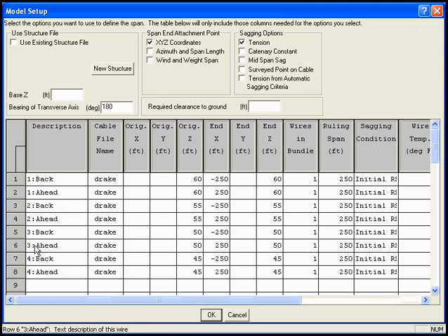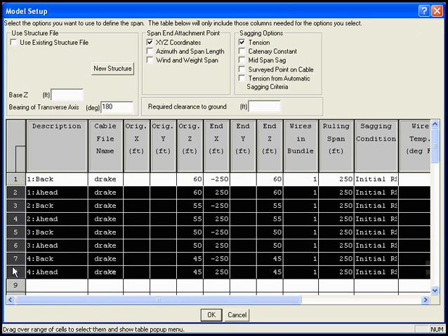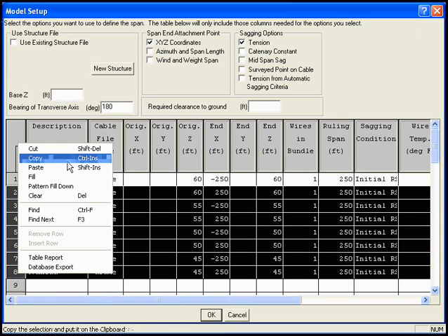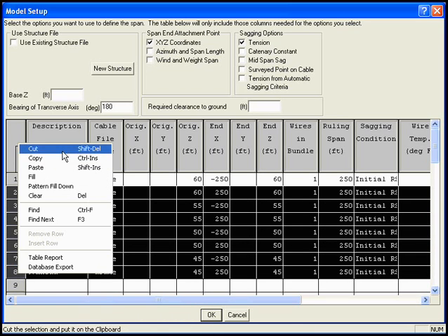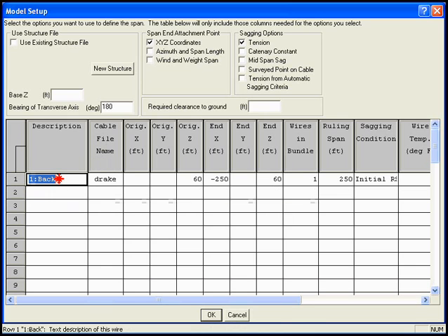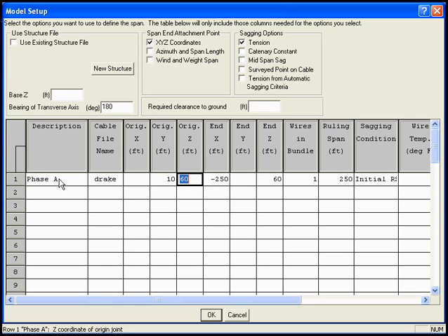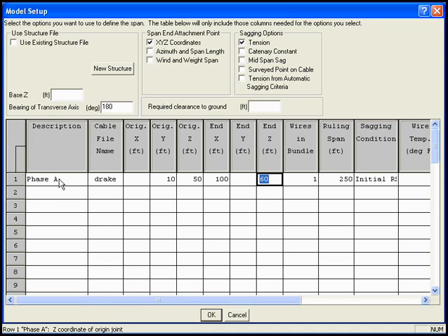It opens up the wizard. Everything is set up. Instead of using the default eight conductors, let's just clear out the last seven, and we'll just start with our first phase, and we'll call it Phase A, and we'll leave it with a drake conductor, and we'll start at 10 feet to the right of center on an A-frame. Then we'll go 50 feet in the air, and we'll project it at 100 feet to a vertical transmission structure at 50 feet at the end. One bundle.